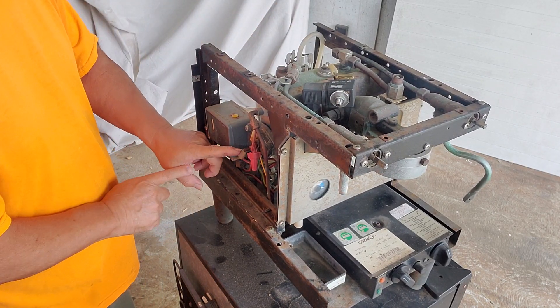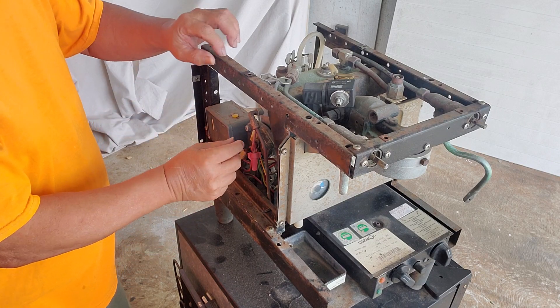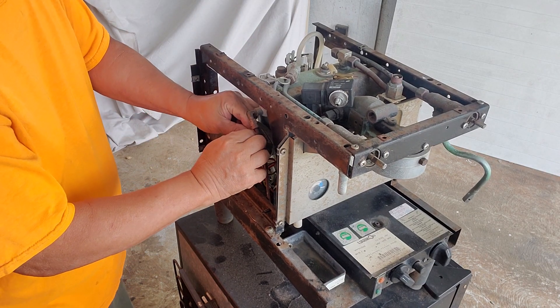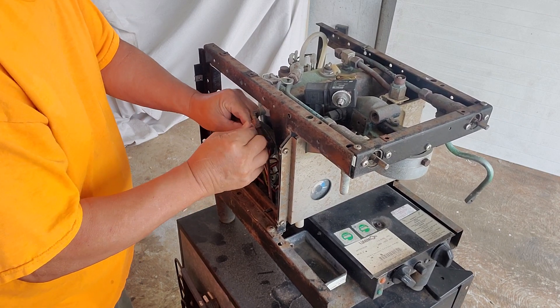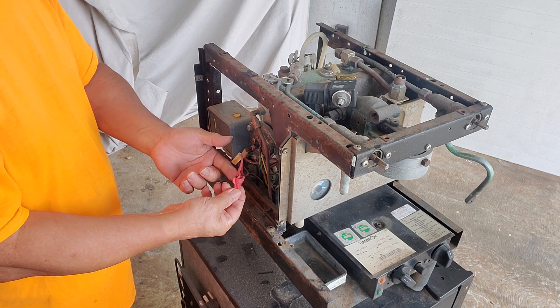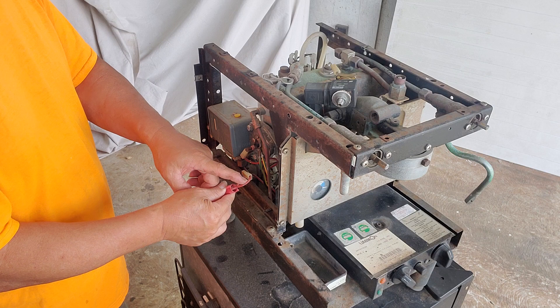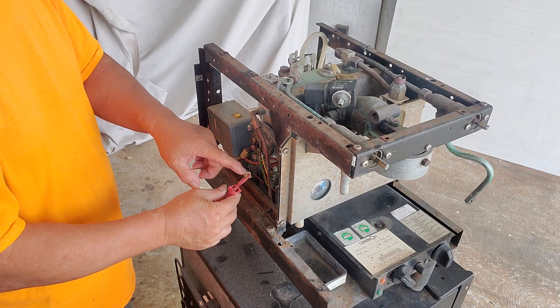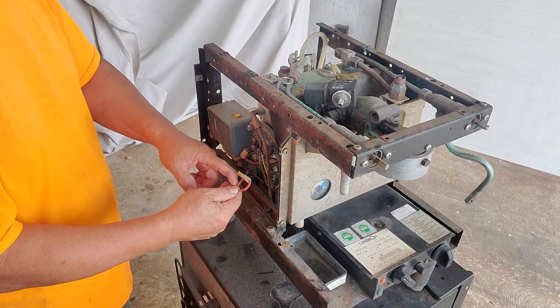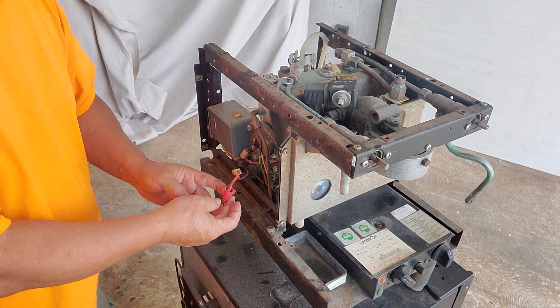What I want to do is disconnect one of the two elements here on the heater. I'll go ahead and disconnect this — as you can see it's been kind of jury-rigged together. I'm going to later replace this with a good wire and have the lug directly connected to the wire instead of using this wire nut. That's one of the things I'm going to clean up.